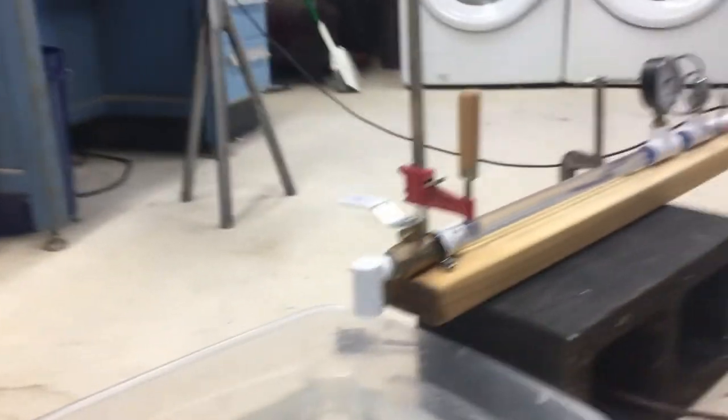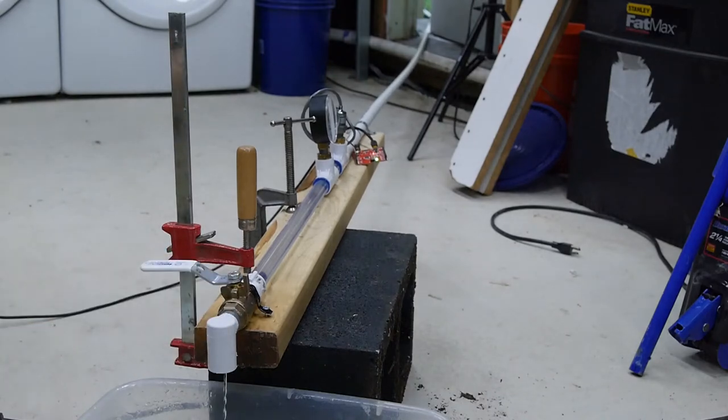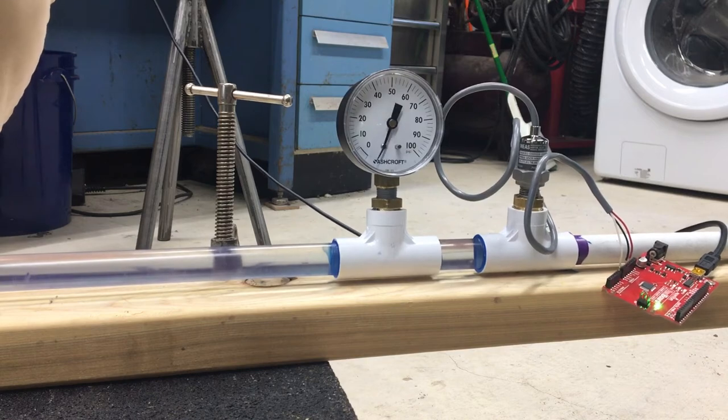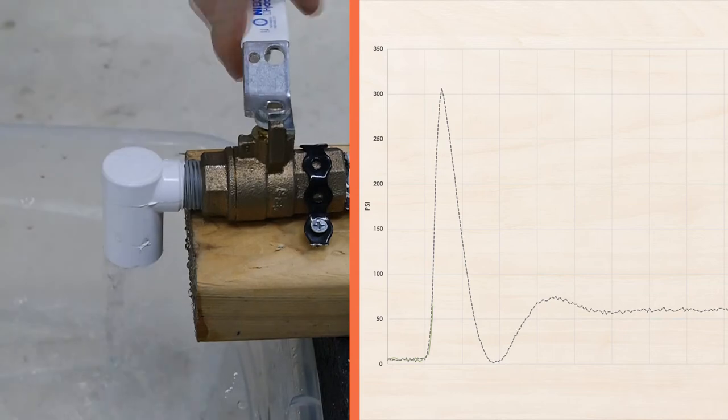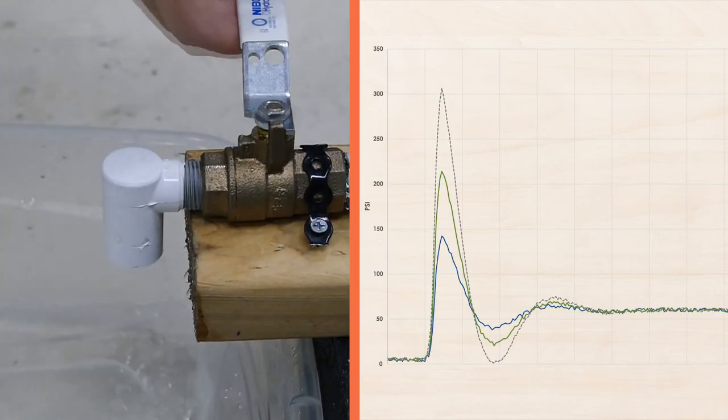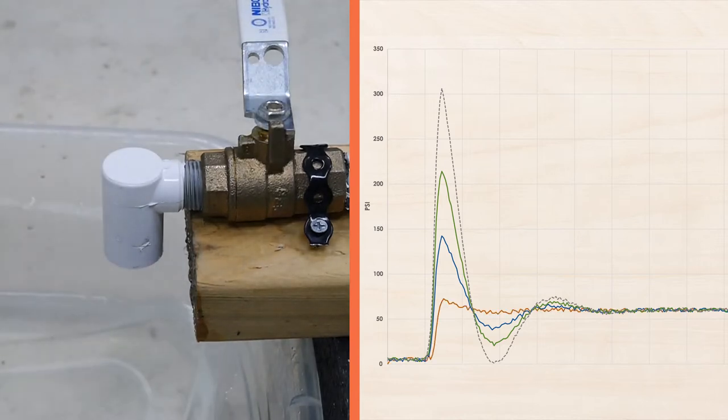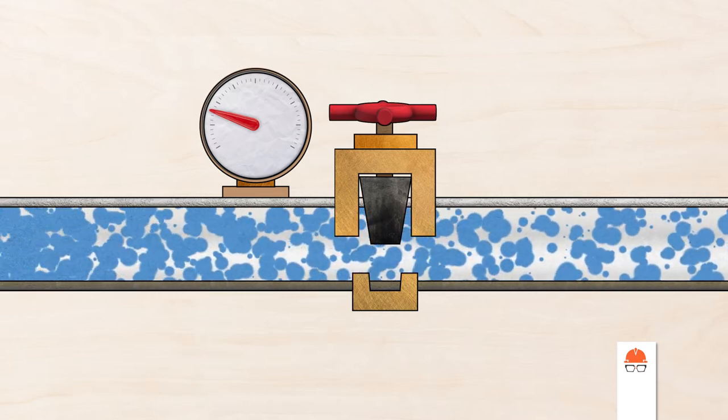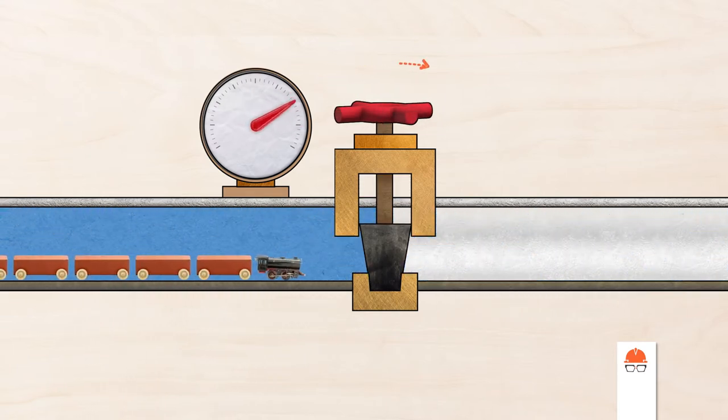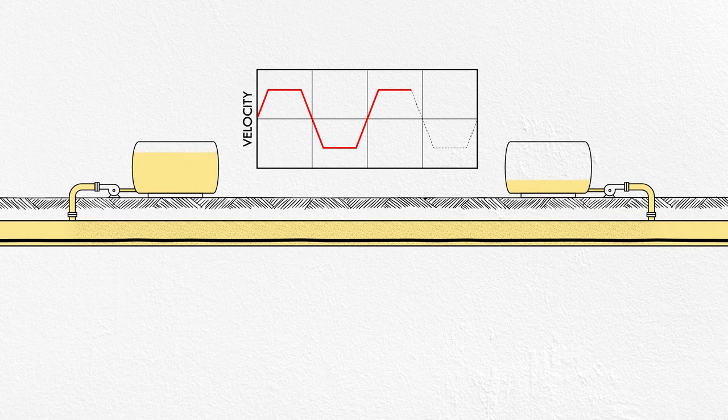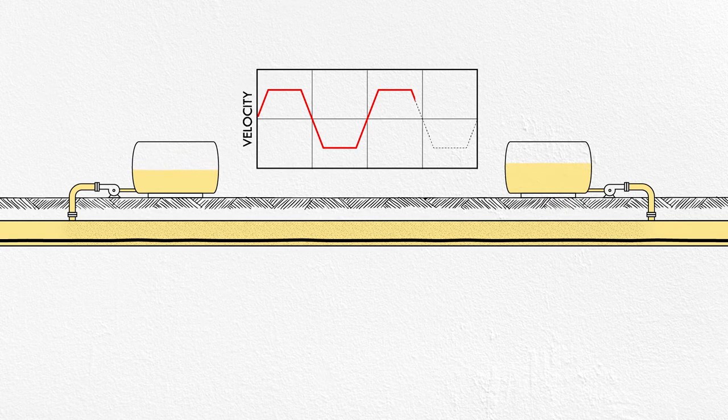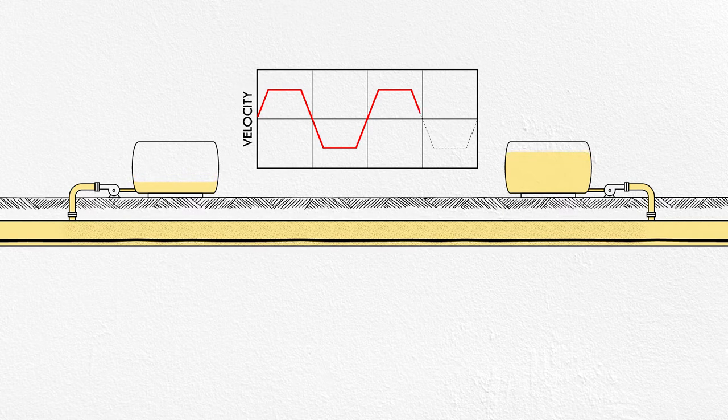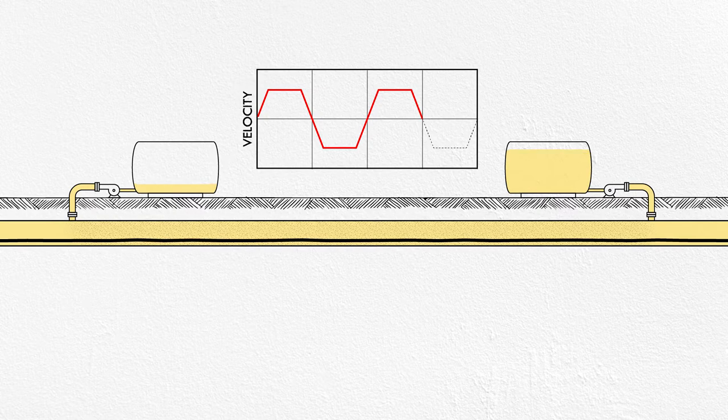However, even at that slow speed, you can't just switch the flow direction in an instant. I have a video all about a phenomenon called fluid hammer, and you can check that out if you want to learn more after this. But I'll summarize here. Moving fluid has momentum, and rapidly changing its velocity can create dangerous spikes in pressure. Water hammer can be a problem in residential homes when taps or valves within washing machines close too quickly. You might hear a pipe knocking against the wall, or in worse cases, you might completely rupture a line. However, in large pipelines that can contain enormous volumes of fluid, reversing a pump can be the equivalent of slamming a freight train into a brick wall. To avoid spikes in pressure, which could damage equipment or rupture the pipe, the pumps at either end of the Scattergood Olympic line would spend the last hour in the six-hour cycle slowing the oil down, providing a smooth transition to flow in the opposite direction for the next cycle.